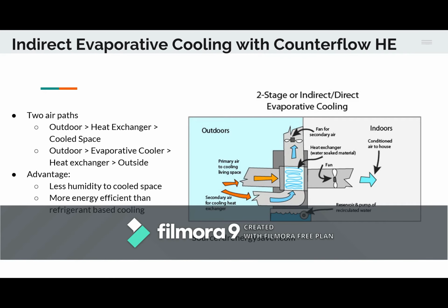Hello everyone, this is Brian, and I will start with an overview of our design. We want to design a cooling system that utilizes indirect evaporative cooling. As seen in the image on the right, indirect evaporative cooling uses latent cooling to reduce the temperature of a secondary airstream. Then the cooled secondary airstream exchanges heat with the primary airstream, lowering the primary airstream's temperature. Finally, the primary airstream goes into the cooling space.